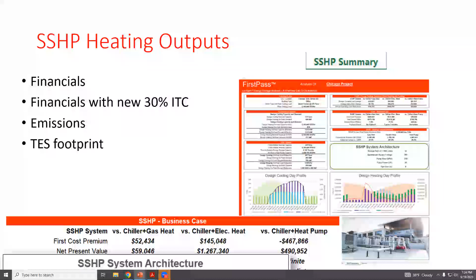Here's something interesting: we took a 300,000 square foot office space with an identical profile and compared it across Chicago and Buffalo - a dirty grid versus what we'd call a clean grid with renewables. A lot of clients have been asking us to look at embodied carbon, the carbon emissions, as opposed to just utility usage. So we took the average CO2 per megawatt hour in these areas.